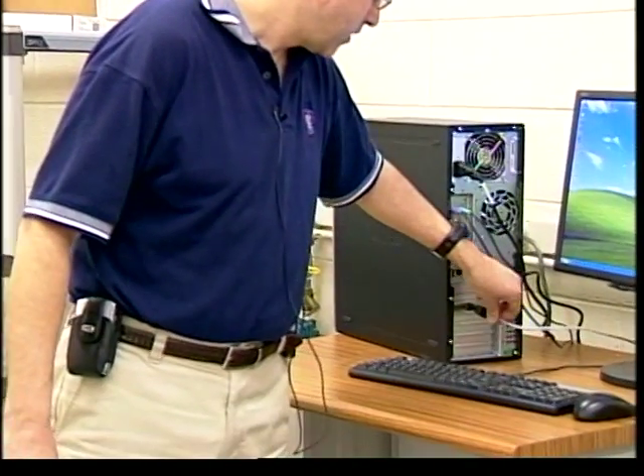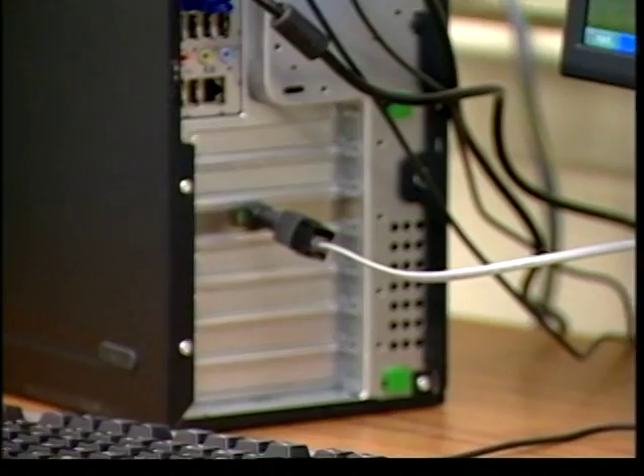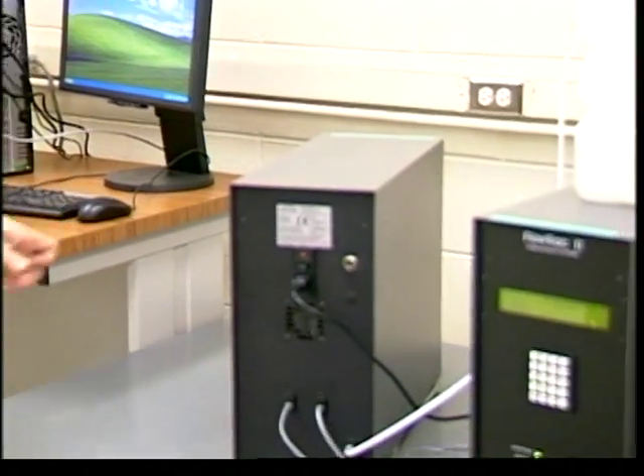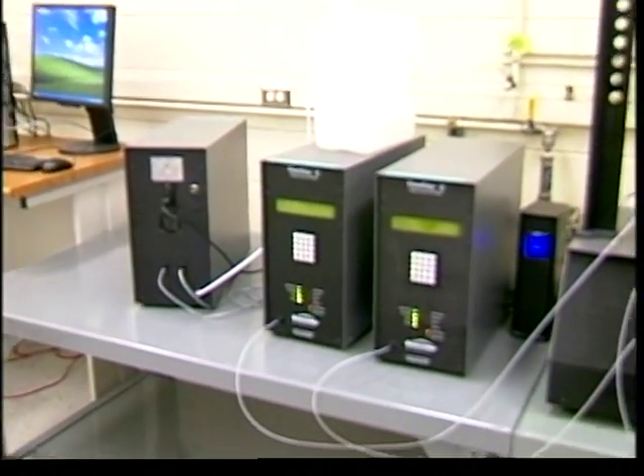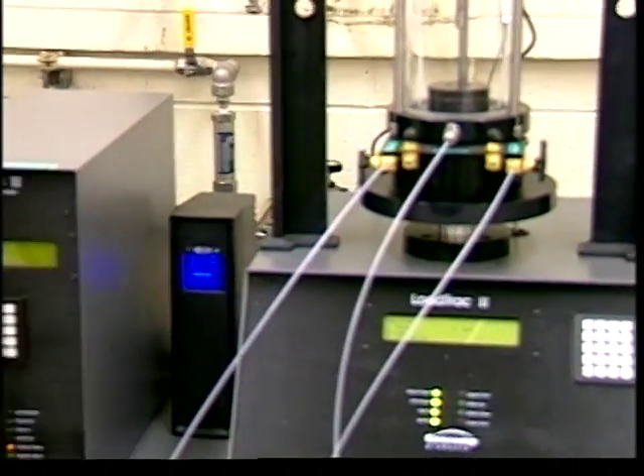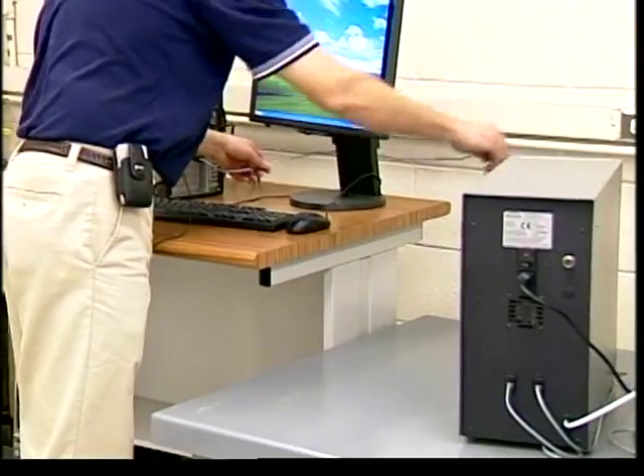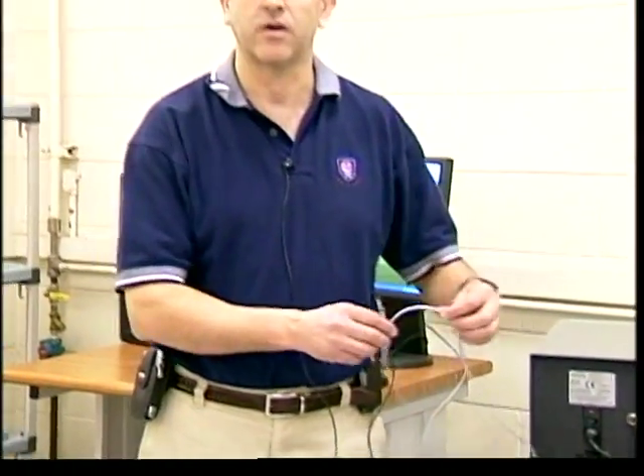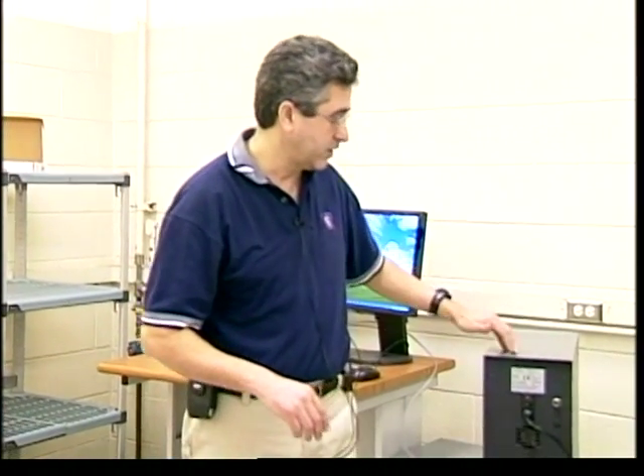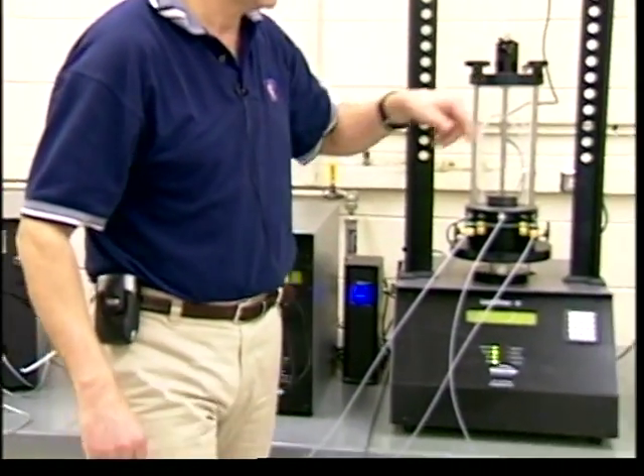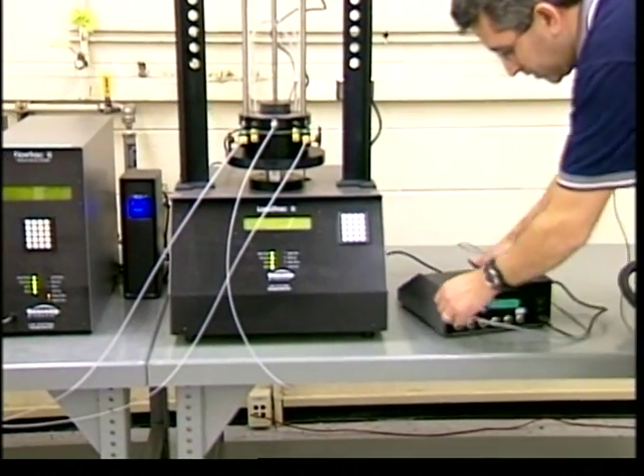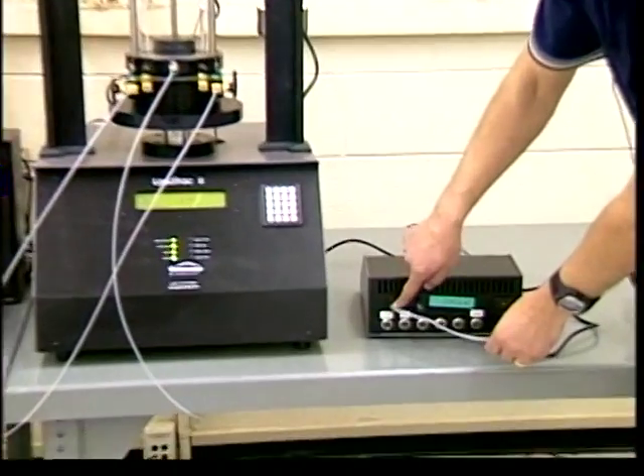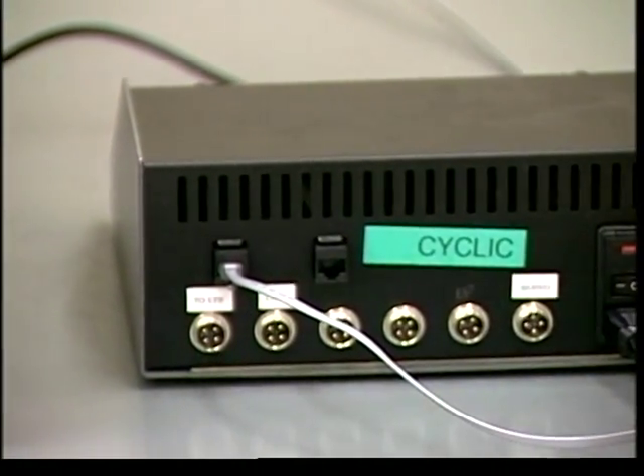Once the card is in, you have the cable. You're going to daisy chain them. So you start from any unit, and you're going to end up with the last unit with what we call a terminator. The terminator goes into the last unit. I can show you. They're stringed together. You've got the network cable that looks like a phone cable. Please do not replace it with a phone cable. It's twisted differently. So you start with one unit, next unit, and so on until the last unit, where you can see on the back the cable coming from the second to last, and the last one will have the terminator. What you see here is a terminator right there, and you put your terminator and you close the loop.